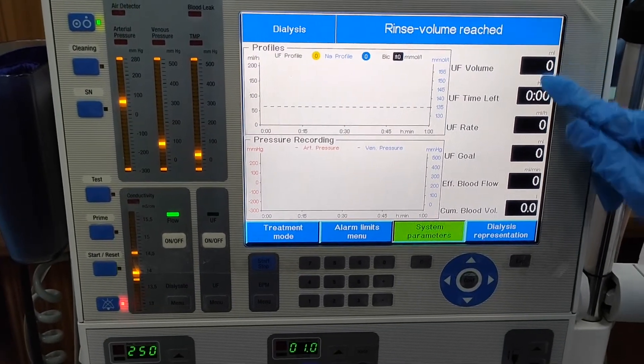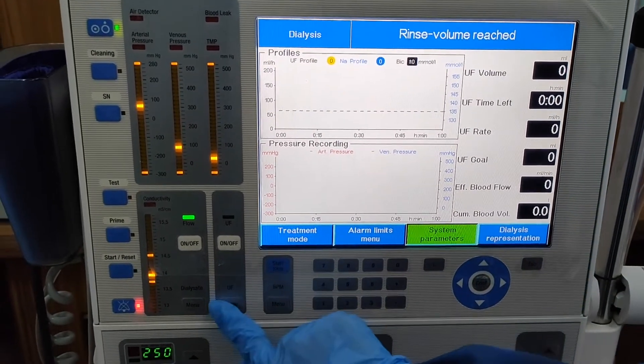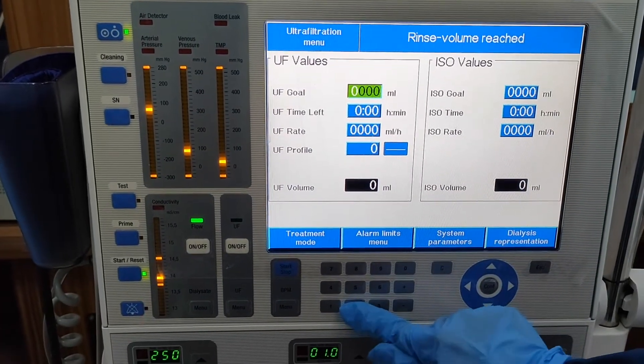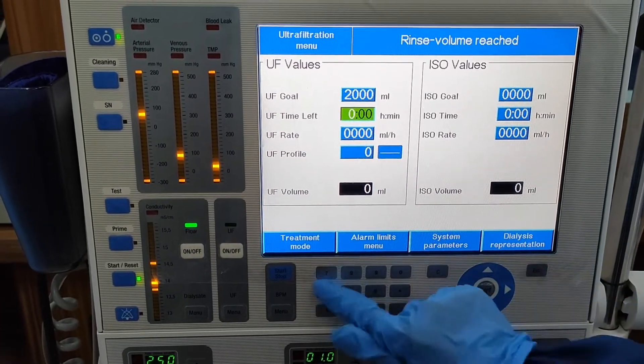You will see that everything went back to zero. So, press menu and make sure to ask the nurse what you will set for the patient's UF Goal.